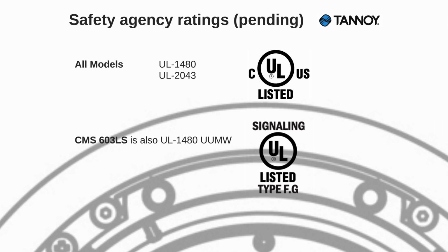These devices will have our UL 1480, 2043 listings, just like the current product line. Importantly, the CMS 603 LS, the life safety version, will be UL 1480 UUMW approved, which is a signaling device approval. This means in voice evac mass notification systems, the speaker will be allowed per NFPA 72 to be used as part of the fire alarm system for tone signaling. So you get away from those little red 4-inch speakers in dual gang boxes that sound great for paging, and move to a real speaker system capable of reproducing alarm tones too.